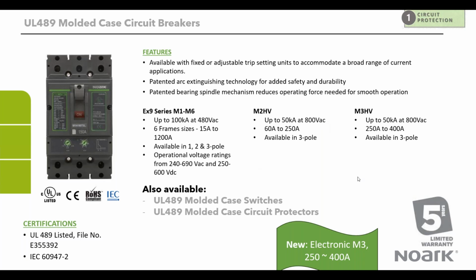So this is an example of our response to those kinds of customer needs. We've got this up to 400 amps at 800 volts and available in 3 poles. We also have the UL489 molded case switches and molded case circuit protectors. A molded case switch is just a circuit breaker without the protection functionality. So it's just a disconnect switch that allows you to make, carry, and break the circuit under normal conditions, and it cannot do that under an abnormal condition.